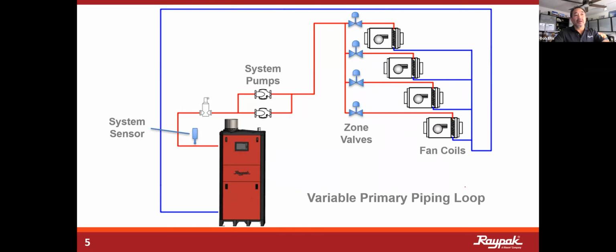Here, if you use a stainless steel boiler, which is a vertical stainless steel fire tube condensing boiler, which is the primary unit that I'm talking about, honestly, the design is outstanding for that. When you consider you're condensing in a boiler, you certainly don't want the products of combustion, the condensate, when that unit is running at peak efficiency, going back into the burner. So making it vertical and making the condensate flow to the bottom of the pan for the flue is ideal, keeping the burner at the top. And they're high mass, so they're a little more forgiving to flow. So you put that into a variable primary piping loop, and everything is great.